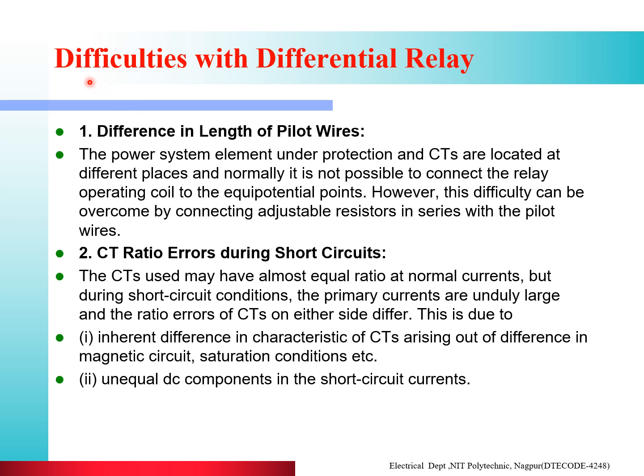Then the difficulties with the differential relay. Difficulties means the abnormalities which may develop in the differential relay. First is the difference in the length of pilot wire. The two current transformers you saw in the diagram are connected by pilot wire, but these current transformers are located between two substations, so the length of pilot wire is in kilometers.